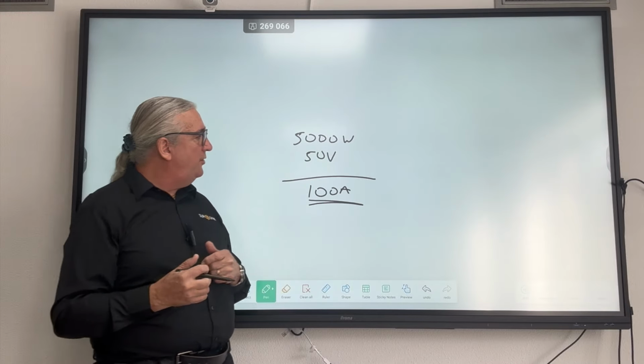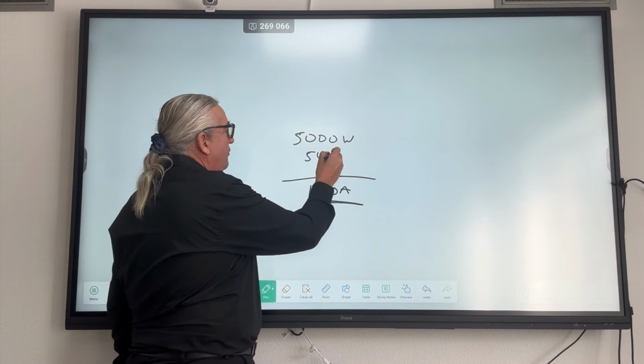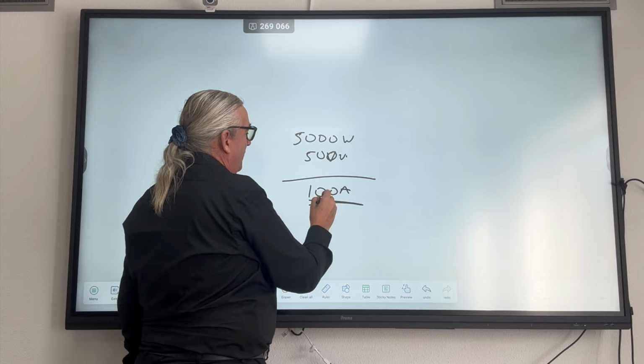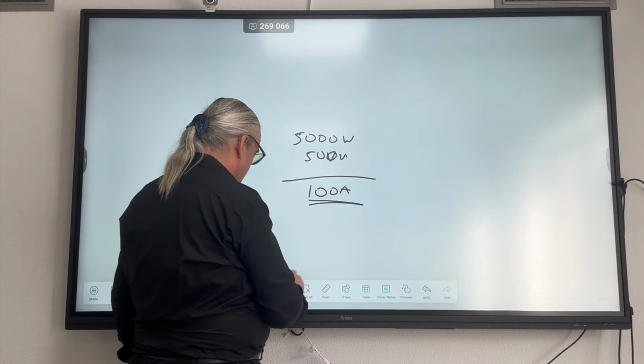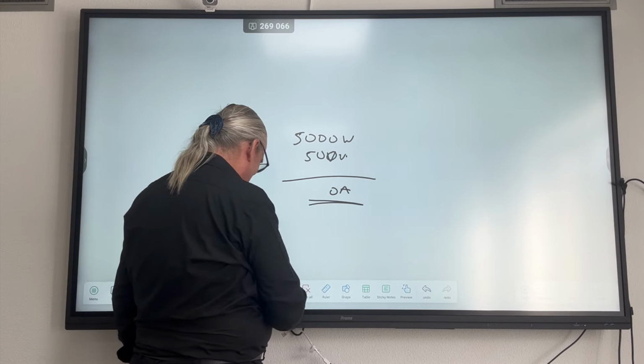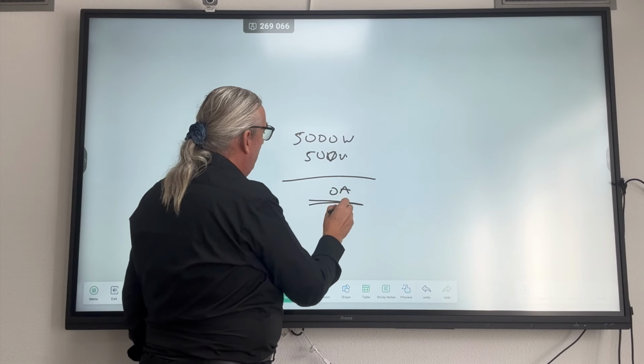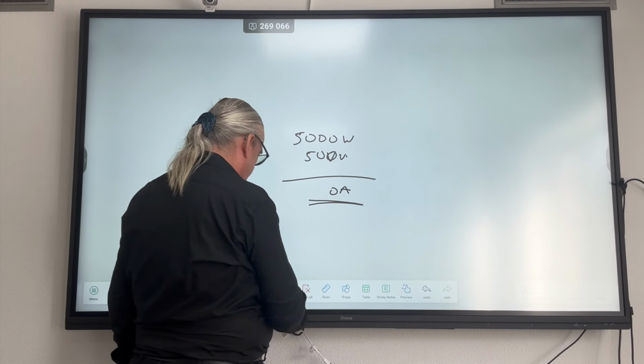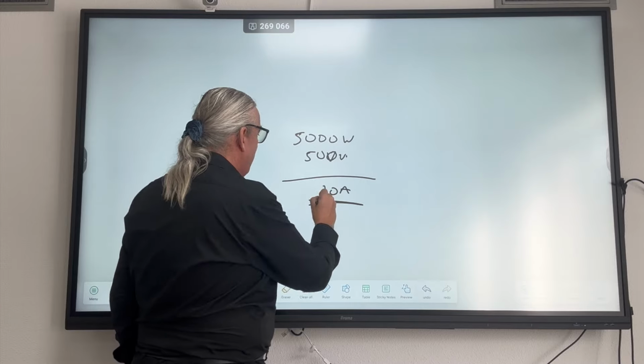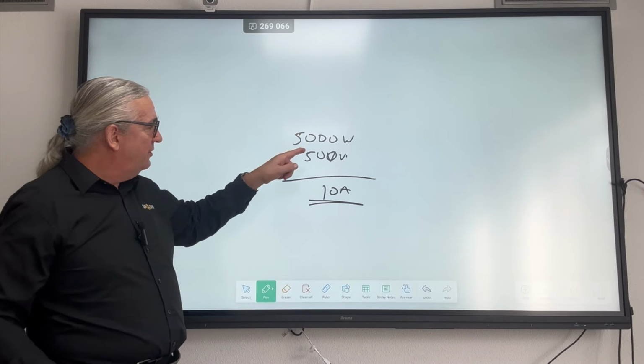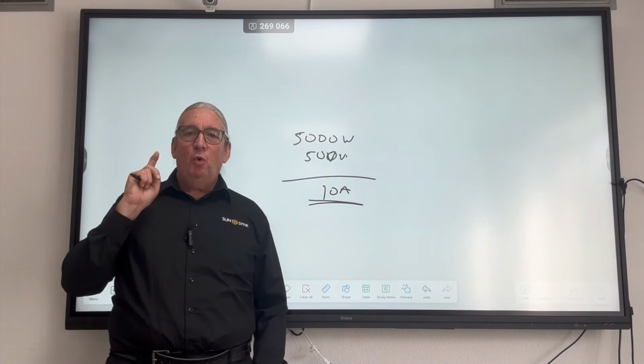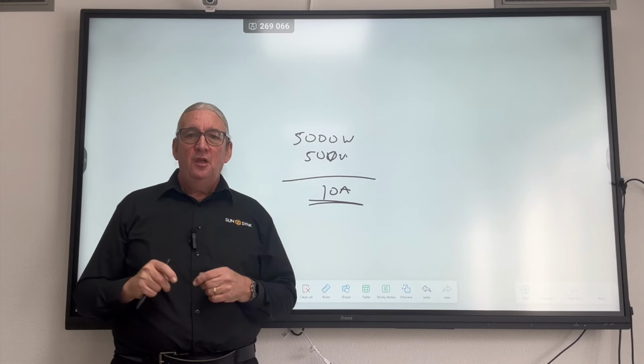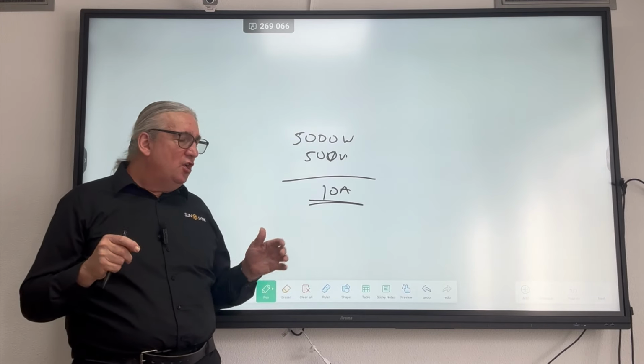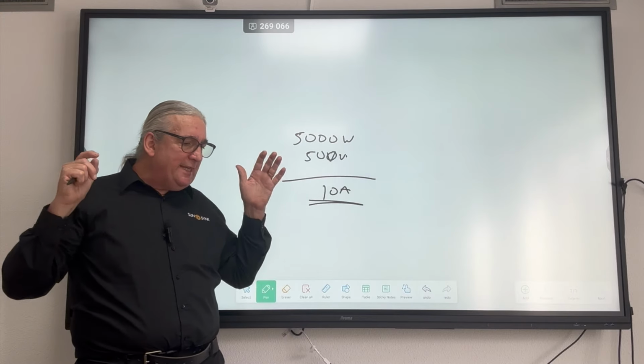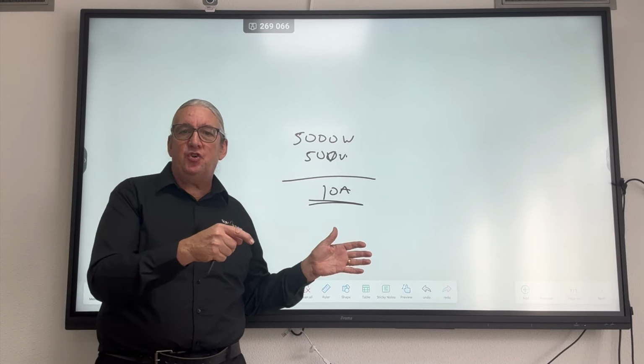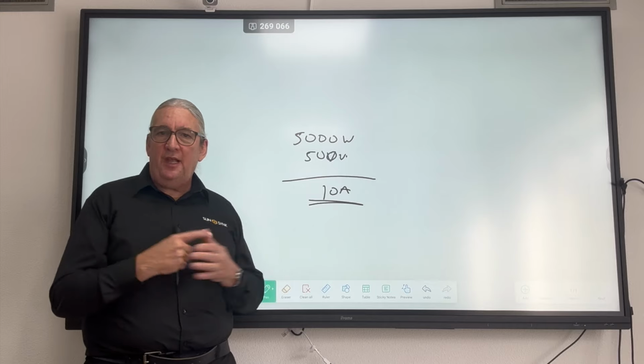But suppose I made that a 500 volt battery instead - the current would become 10 amps. 5,000 watts over 500 volts is 10 amps, which is one tenth of the current. So you're transferring some of the technology from the inverter into the battery, but your current is a lot less.